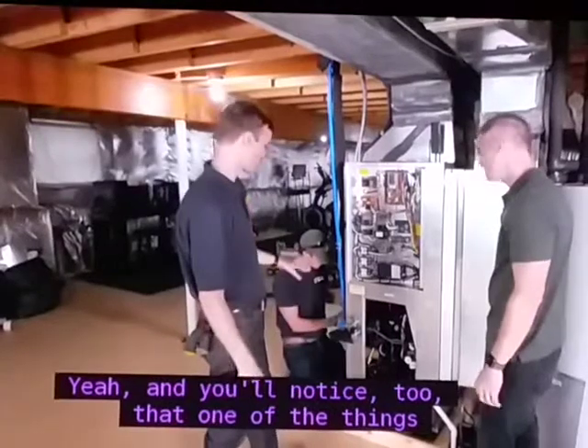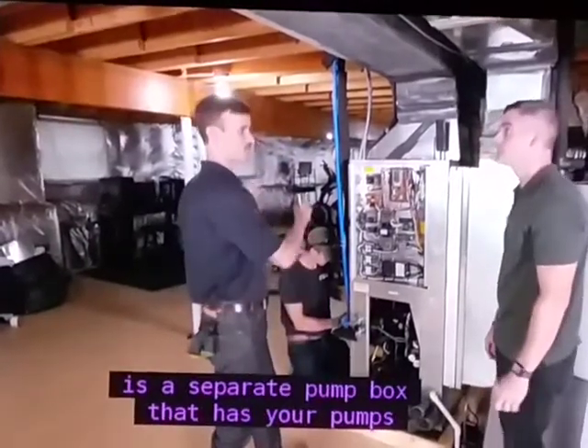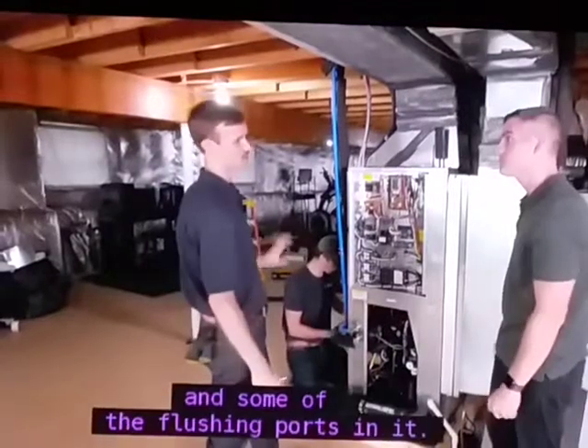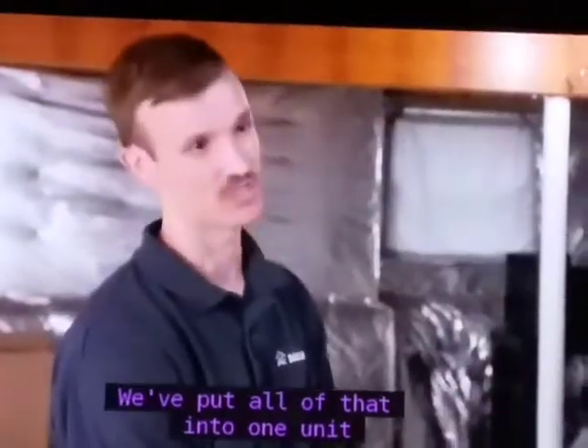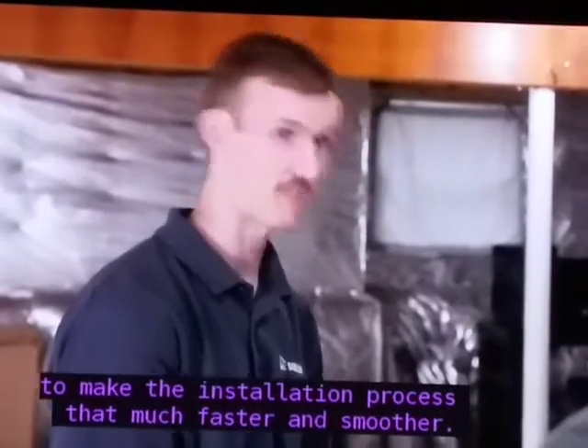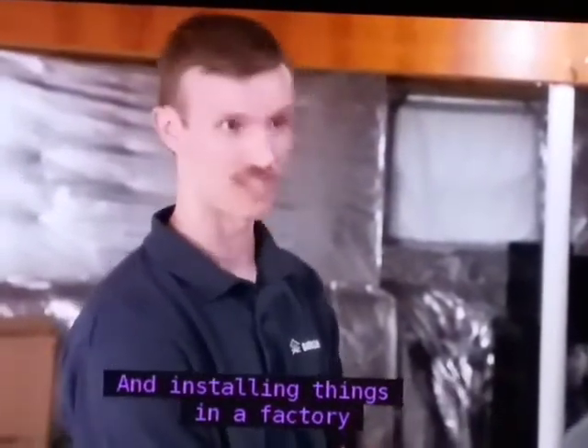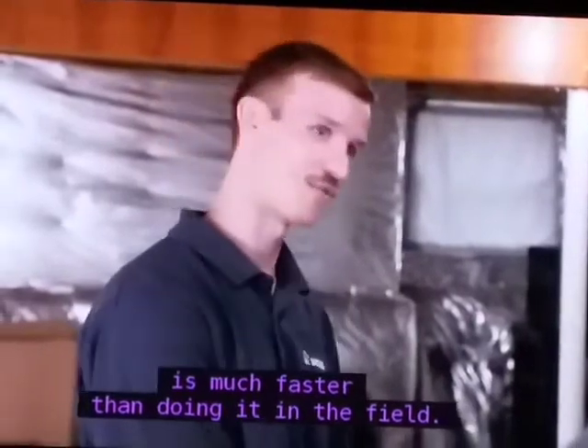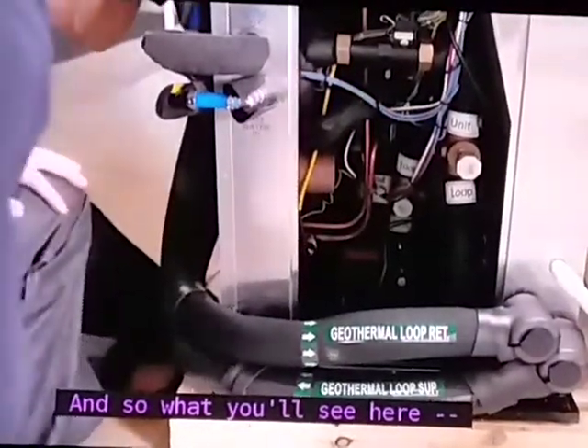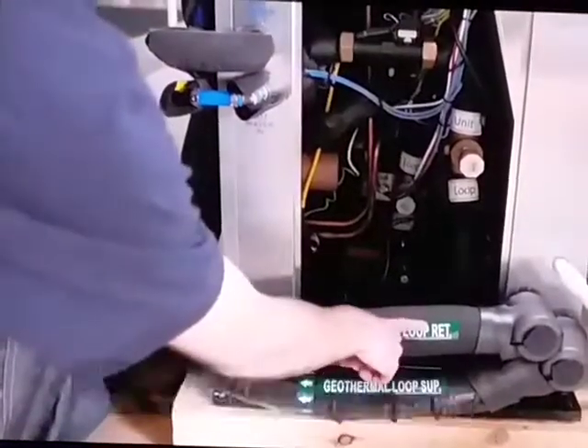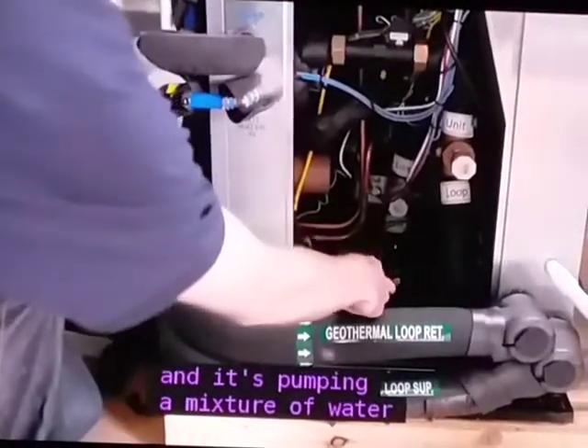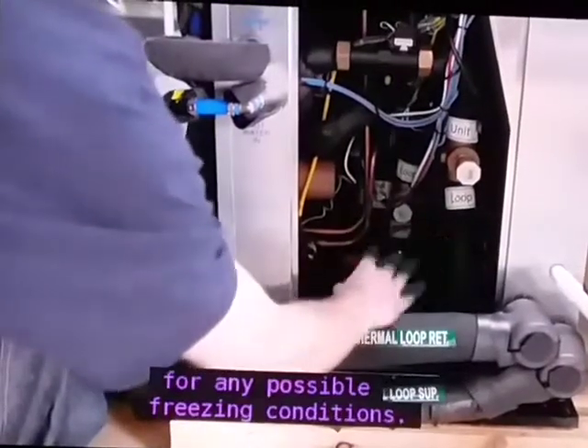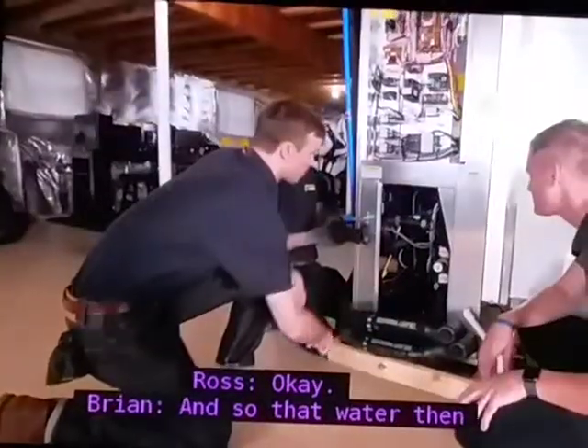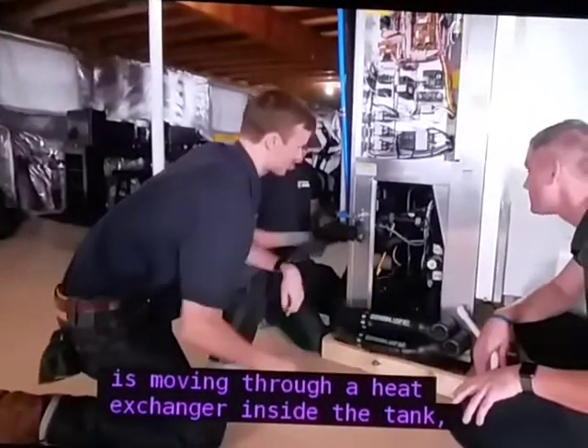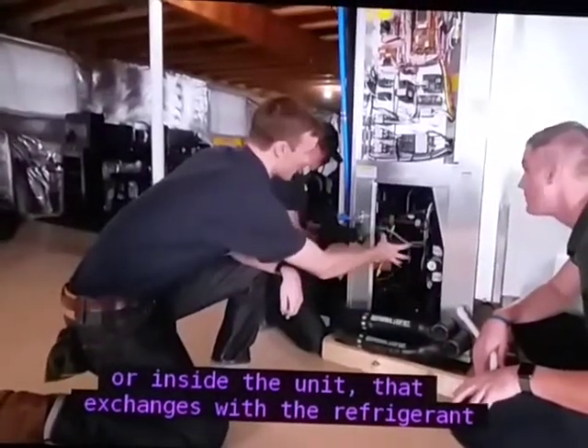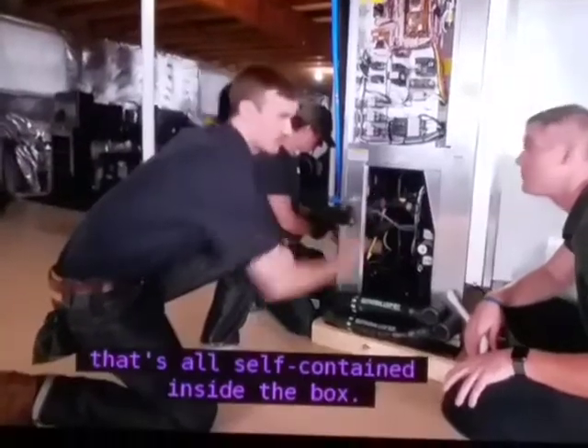Yeah, and you'll notice too that one of the things you'll typically see in a geothermal system is a separate pump box that has your pumps and some of the flushing ports in it. We've put all of that into one unit to make the installation process that much faster and smoother. And installing things in a factory is much faster than doing it in the field. Sure. And so what you'll see here is two pumps that pump through this piping and out to our geothermal well. And it's pumping a mixture of water and a little bit of glycol just to account for any possible freezing conditions. Okay. And so that water then is moving through a heat exchanger inside the unit that exchanges with the refrigerant that's all self-contained inside the box.